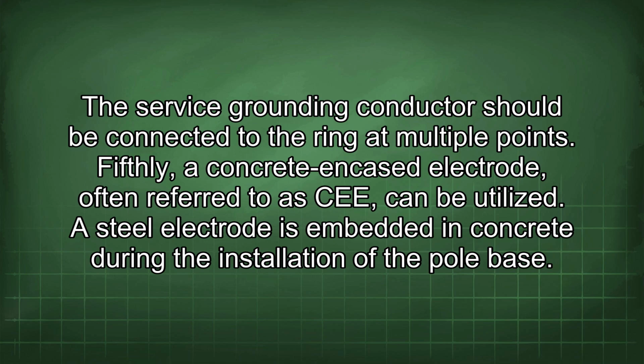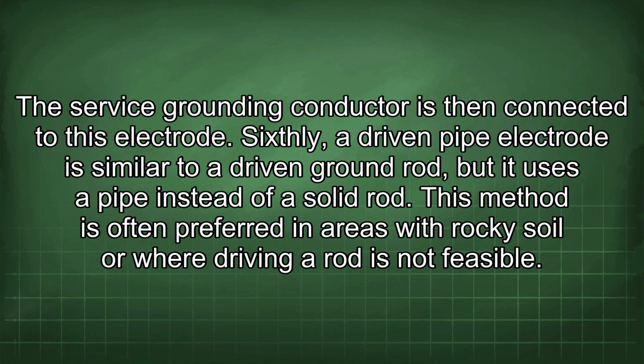Fifthly, a concrete encased electrode, often referred to as CEE, can be utilized. A steel electrode is embedded in concrete during the installation of the pole base. The service grounding conductor is then connected to this electrode.